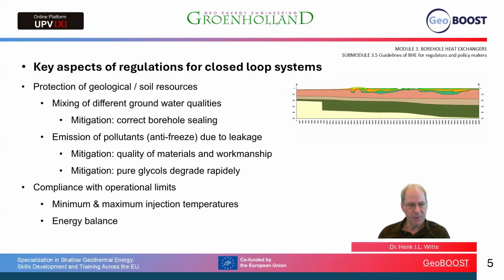Another aspect is to have compliance with operational limits. For instance, we want to have a maximum and minimum temperature, a maximum injection temperature and a minimum injection temperature. For instance, an injection temperature not below -3 degrees, because we want to prevent freezing of the soil and freezing of the borehole heat exchanger. Another aspect can be energy balance. In the Netherlands, for instance, we want to prevent the ground from heating up, so we allow a net heat extraction from the ground, but we do not allow a net heat injection of energy into the ground.